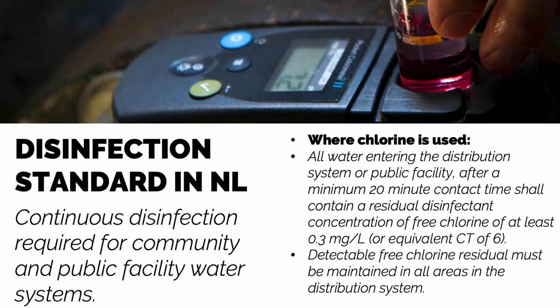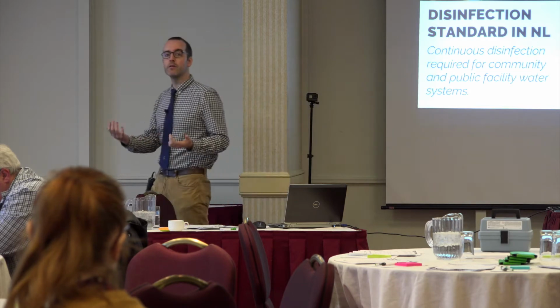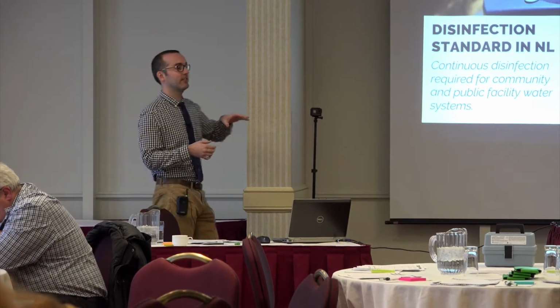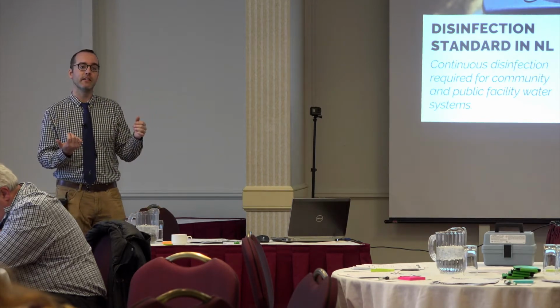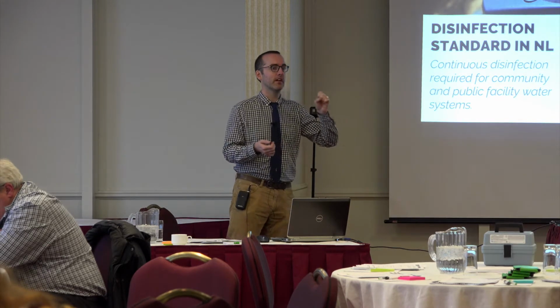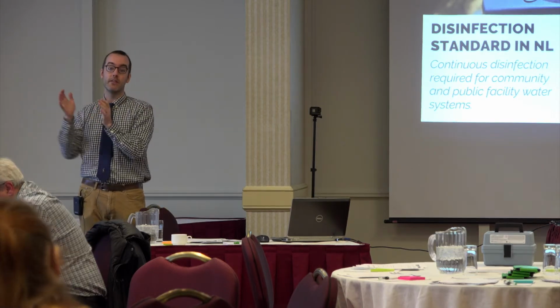There's a standard to that system's design where, thinking back to Henrietta Chick in the 1900s, she said, add the right amount of disinfectant for the right amount of time. So we still have that today. Water, as it enters the distribution system on its way to the first user, has to have had the right amount of time to disinfect, and it had to be at the right strength. That's something called the CT factor. Probably some of you are familiar with it, some of you might not be. Your system was designed to give a CT equivalent of 6. So the concentration was large enough and the time was long enough. They came together to say that would be secure for this system.